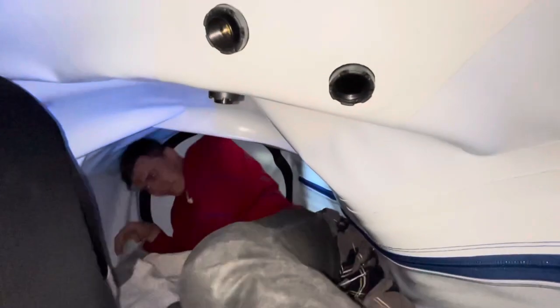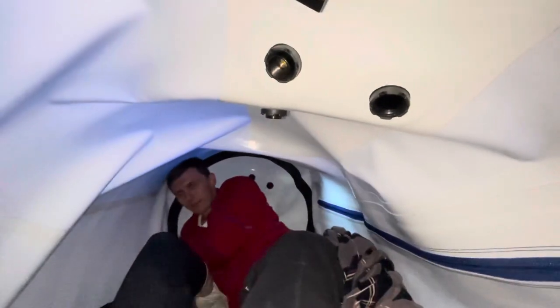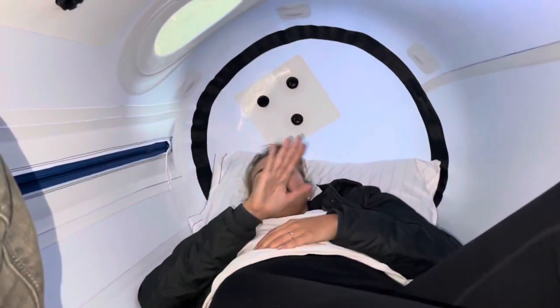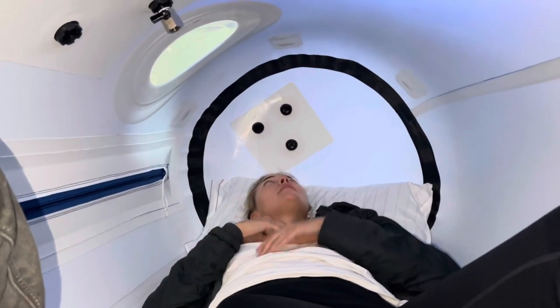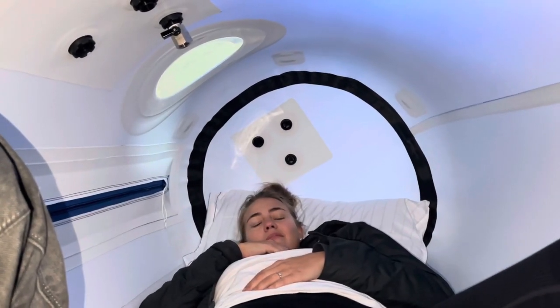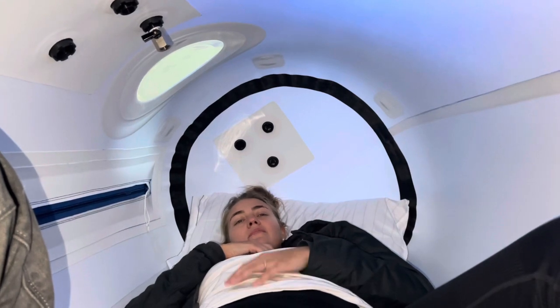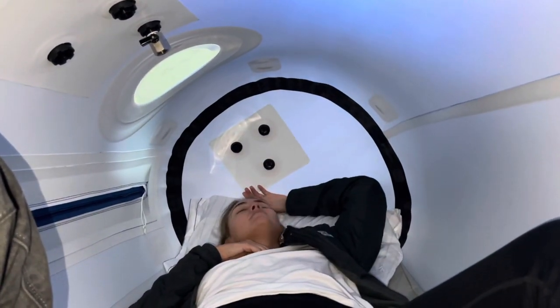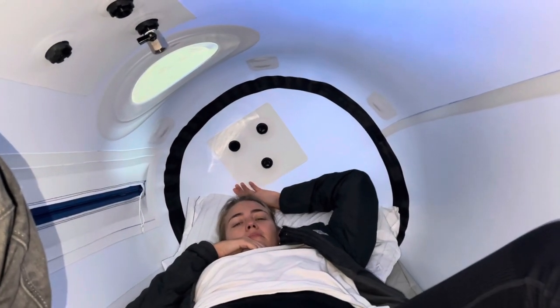We are too big for this. Oh my goodness. Okay, stay on your side. So behind Dasha are the safety pressure relief valves — there are two of them. One is an auxiliary, just blocked off. What they're doing is releasing pressure right now; you can hear air moving out. That means the air pressure inside the chamber has reached the setting, so we're at 1.3 barometric pressure right now. The open-and-close valve is closed.